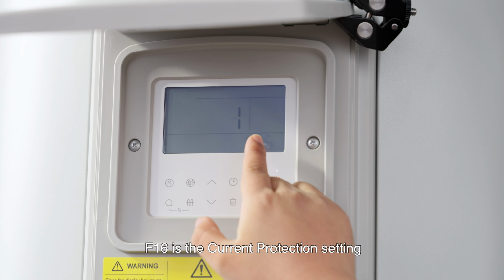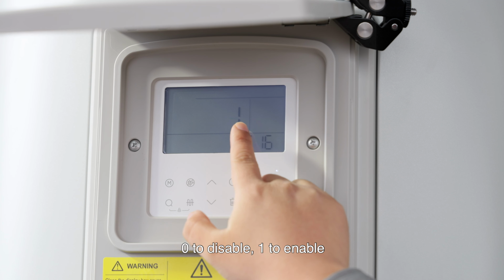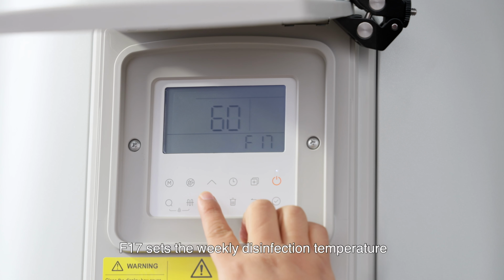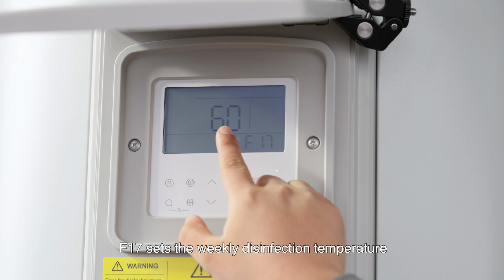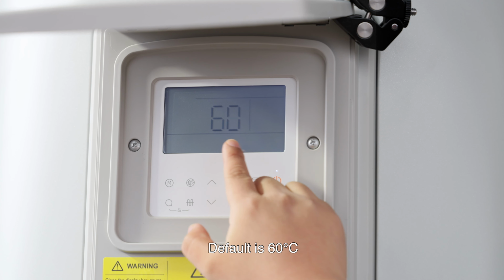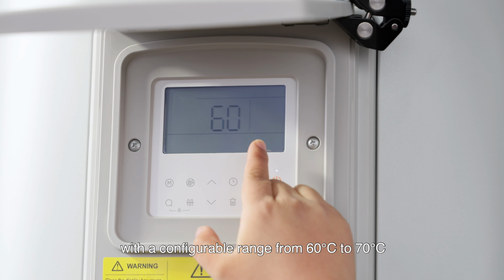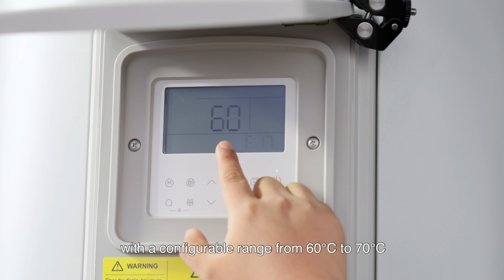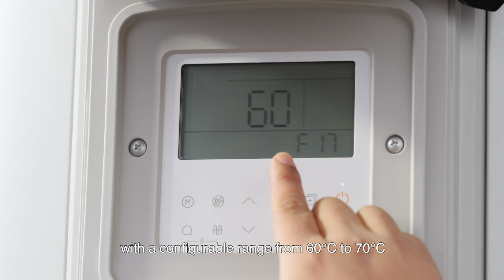F16 is the current protection setting. 0 to disable, 1 to enable. F17 sets the weekly disinfection temperature. Default is 60 degrees Celsius, with a configurable range from 60 degrees Celsius to 70 degrees Celsius.